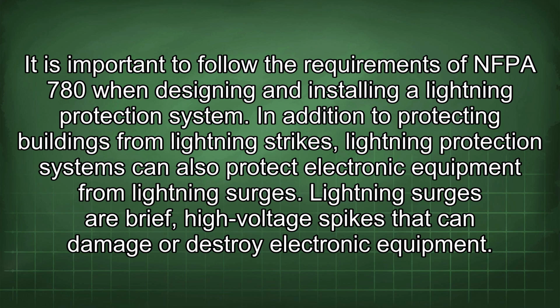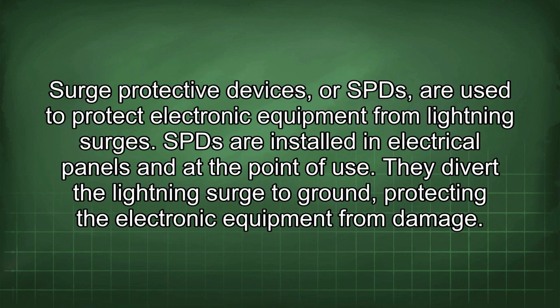In addition to protecting buildings from lightning strikes, lightning protection systems can also protect electronic equipment from lightning surges. Lightning surges are brief, high-voltage spikes that can damage or destroy electronic equipment. Surge protective devices, or SPDs, are used to protect electronic equipment from lightning surges. SPDs are installed in electrical panels and at the point of use. They divert the lightning surge to ground, protecting the electronic equipment from damage.